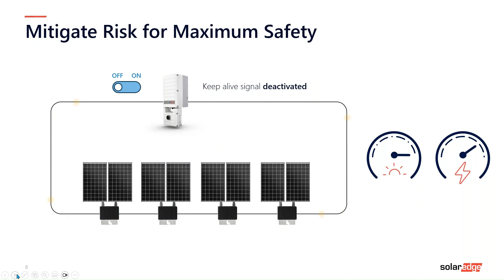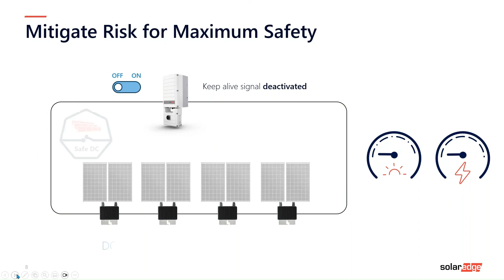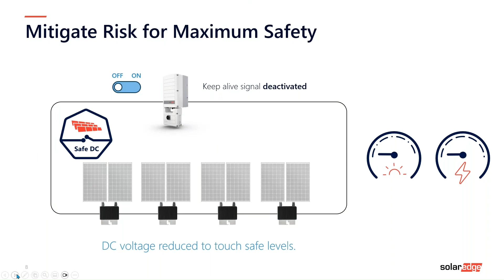Now press the button again. One more time. Switch goes to off, which could basically be any of the issues that I've said. You turn it to off, and then what will happen is the keep alive signal will disappear. The power optimizer will go back to safe mode, and the irradiance is still there, but the power generation is 0 and the voltage is 0. Well, the voltage is not 0, the voltage is under 50 volts for commercial, but in realistic terms, that's about 30 volts. Now, bearing in mind, the SafeDC voltage requirement is 120 volts, so we are miles under what is required.